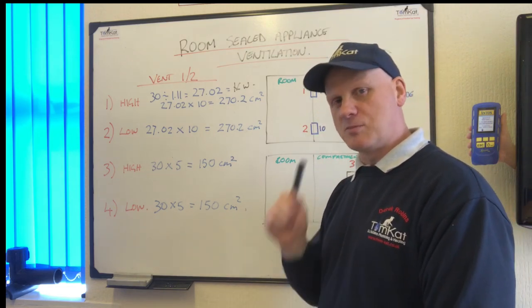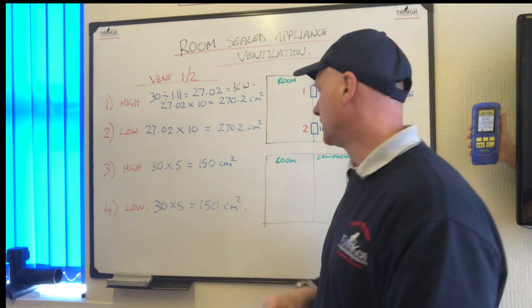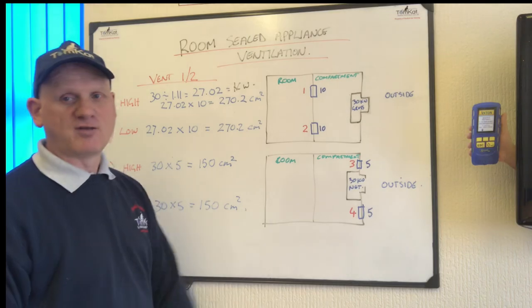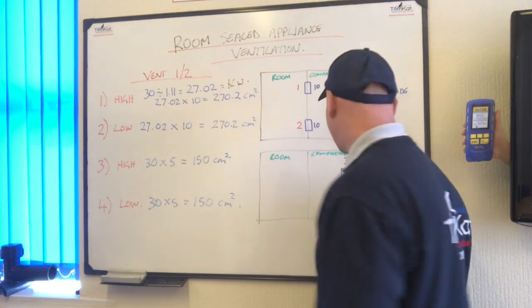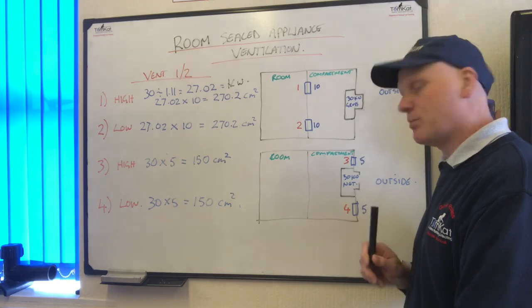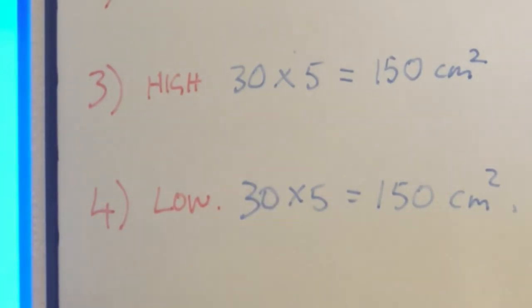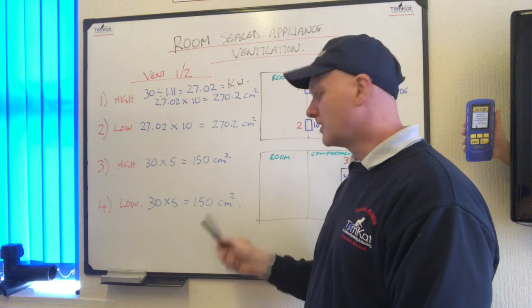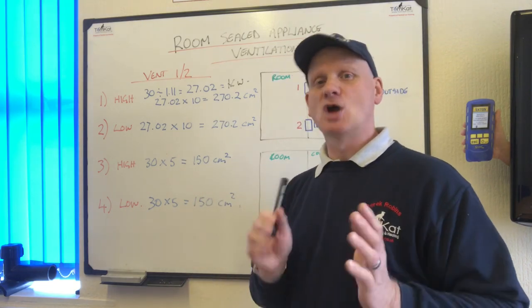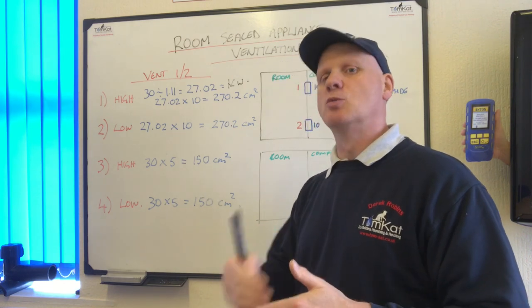When doing room sealed compartment ventilation for cooling, the two vent figures are always the same — unlike open flued appliances. Now for outside air (5 and 5), using a 30 kW net boiler: 30 × 5 = 150 cm² high vent, and 30 × 5 = 150 cm² low vent. The key difference from open flued: room sealed cooling has equal high and low vents, whereas open flued has the bottom vent double the top.